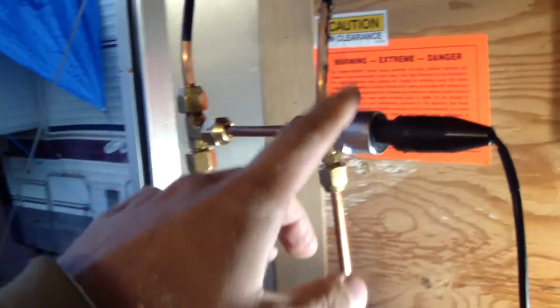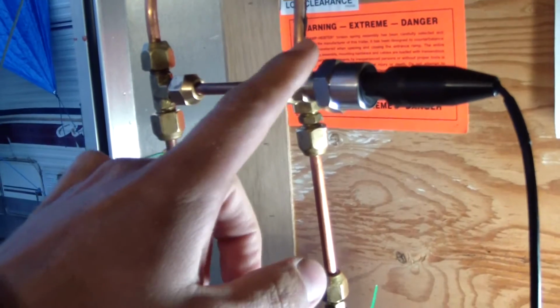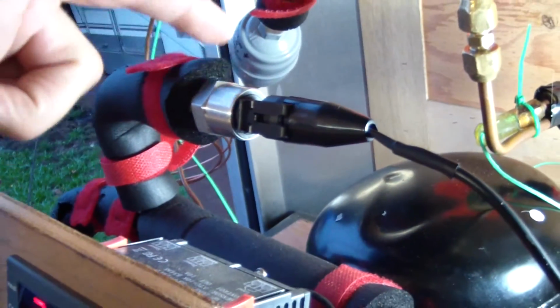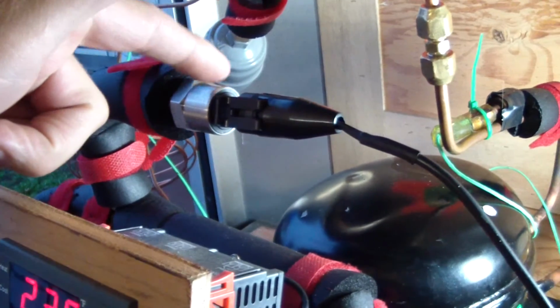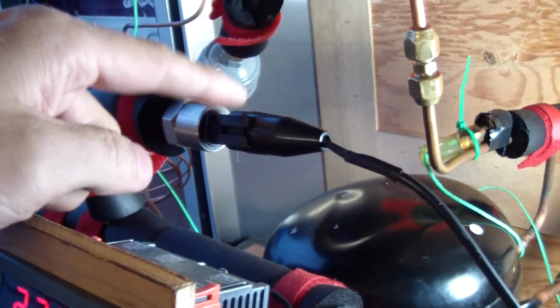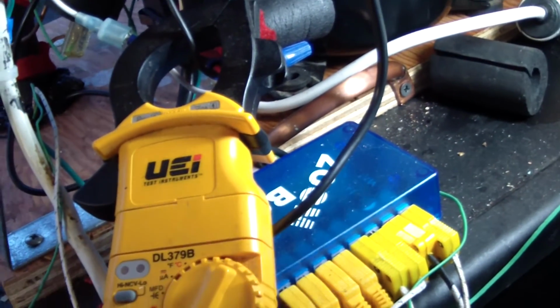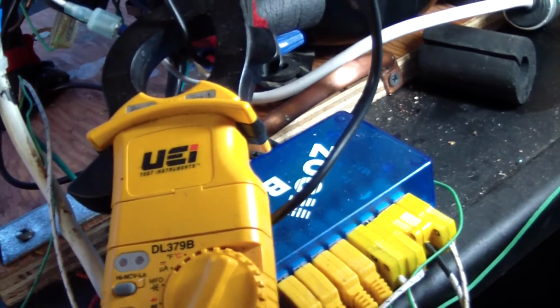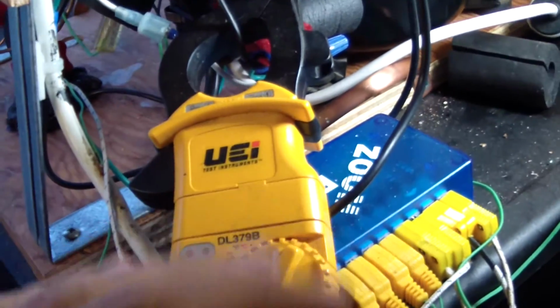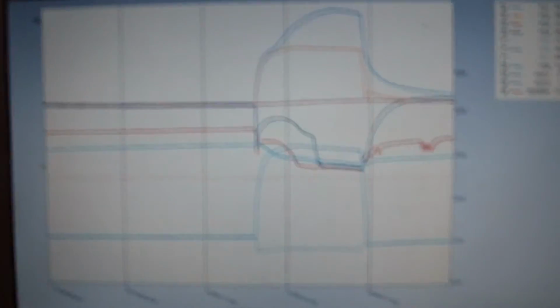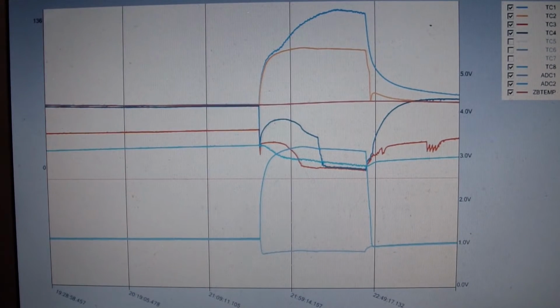In addition to that, we've added some pressure transducers. We have two of them, one on the high side and then one here on the low side. Those things output 0.5 volt DC to 4.5 volt DC with a 5 volt DC input. Those are wired right into the Zoom box temperature logger where all the thermocouples are installed. We have 8 thermocouples, so we're also taking temperatures like ambient temperature, box temperature, a couple different places, the propylene glycol, non-eutectic solution.